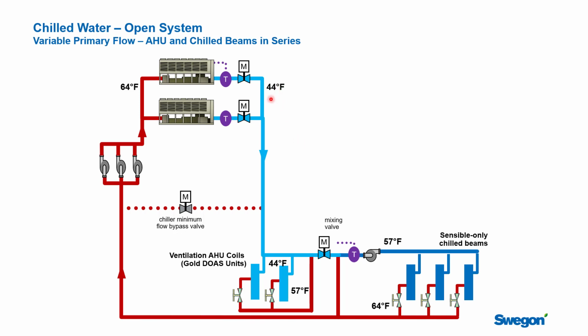Well, we've modified the temperatures here so that they work out ideally. So we've gone to 44 degree water. There's nothing unusual about that. And we're going to design these coils in our air handling units so that at design conditions, we will heat that water from 44 to 57 as we cool and dehumidify that primary air. Well, 57 degrees is the supply water temperature that we want to send out to the chilled beams. And so really quickly you would say, wow, this looks really promising, right? We can flow the water first through one application and then in series, run that water through the chill beams and bring it back and have a very nice 20 degree delta T across the plant.